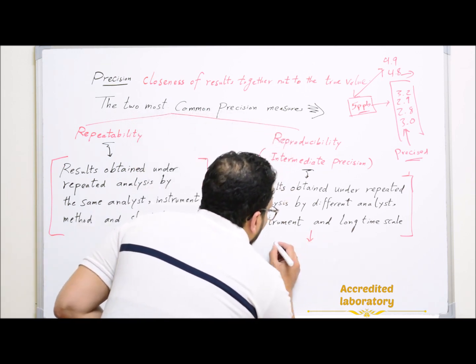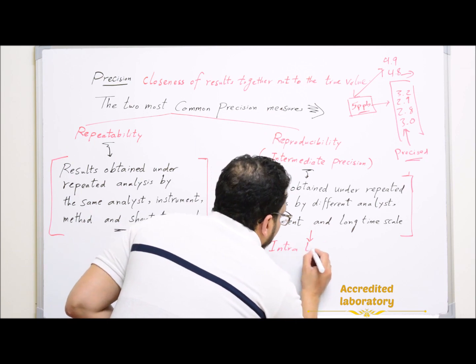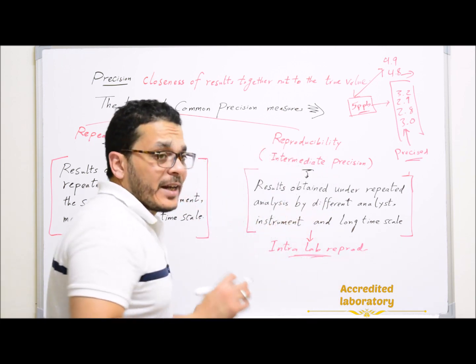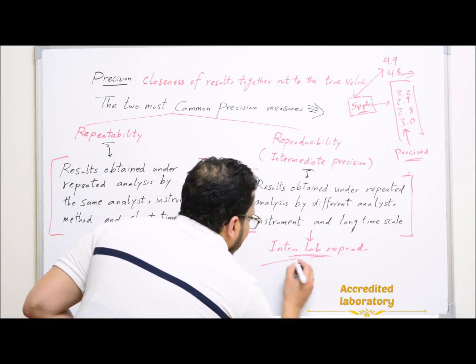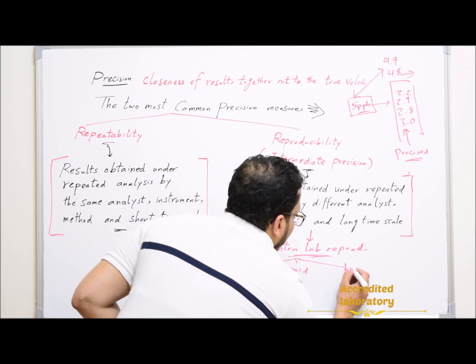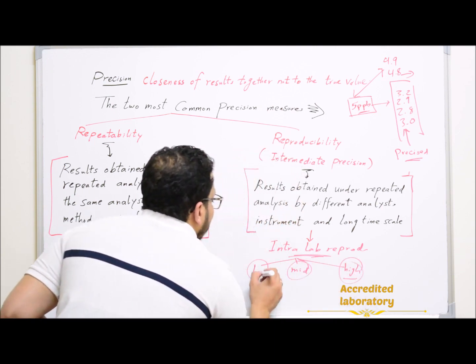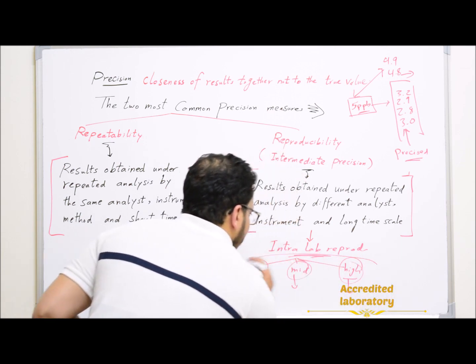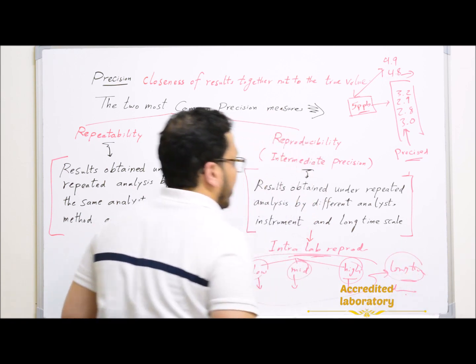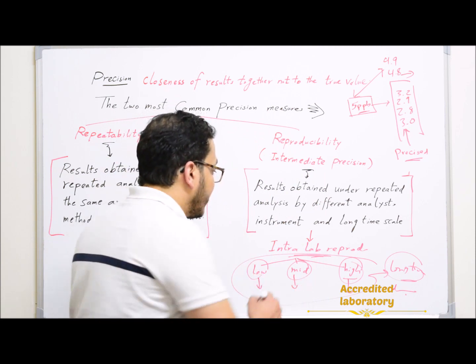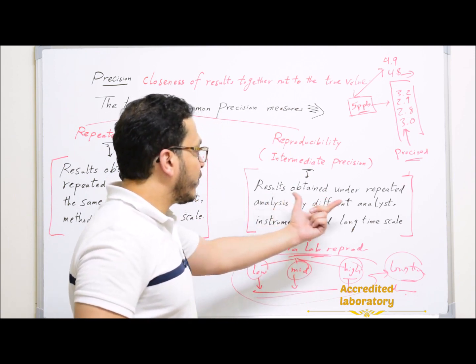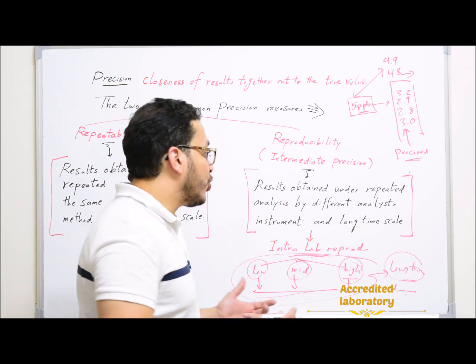In this case, you can do intra-lab reproducibility. You will make replicate analysis but at different levels — you will select three different levels: low level, mid level, and high level — and make replicate analyses from each one. These levels will be done on a long time scale. Similarly, you can also use a different analyst with the same instrument, but select different levels. This is how to achieve this performance parameter if you cannot change analysts or instruments.